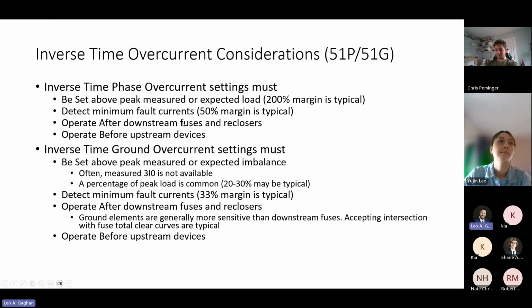So really the goals of this inverse time are, first off, you have to be set above your peak loading. You can't be tripping on loading. That's a normal operating condition. People need power. You can't be tripping them off for normal load. So that's your first goal. So usually you would figure out, hey, I've got 1,000 houses connected to this distribution line, the most power they could ever use would be 2,000 amps, and I have to be set above that.